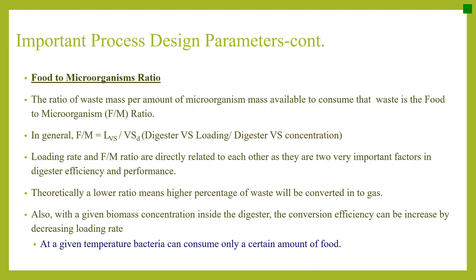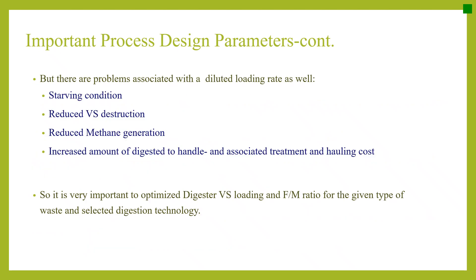At a given temperature, bacteria can consume only a certain amount of food. But there are problems associated with too dilute a loading rate as well — if bacteria are given too little food, starving conditions result, causing reduced VS destruction, reduced methane generation, and increased amount of digestate to handle with associated treatment and hauling costs. It is very important to optimize the digester VS loading and FM ratio for the given type of waste and selected digestion technology.